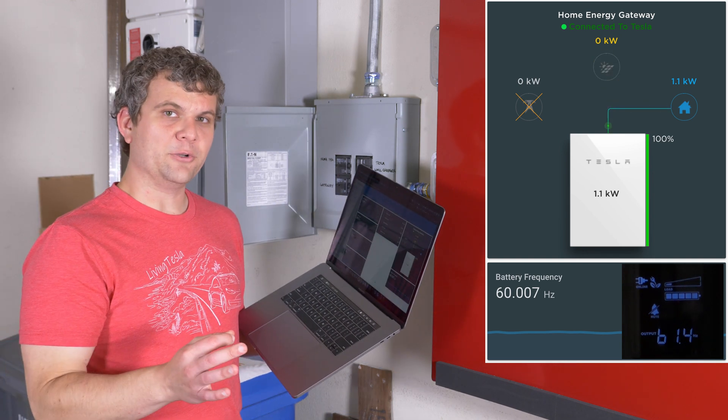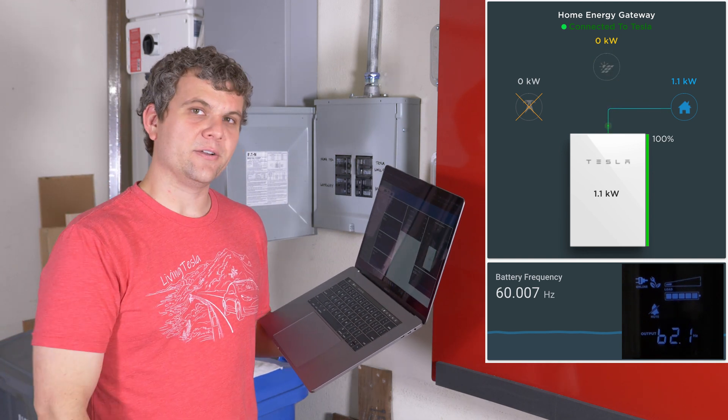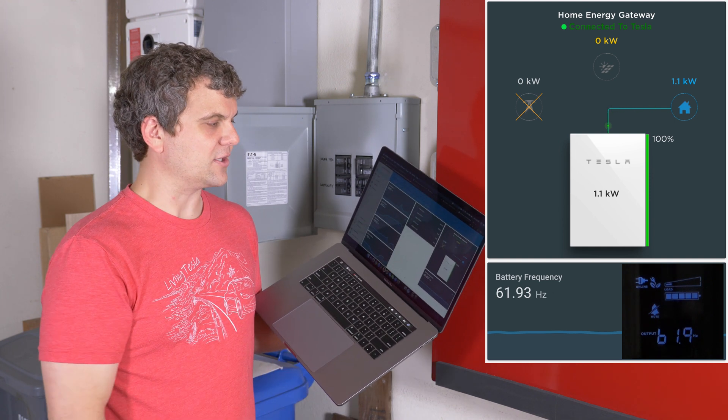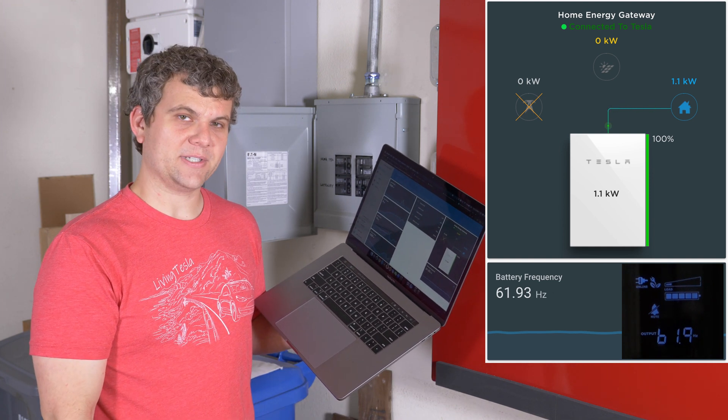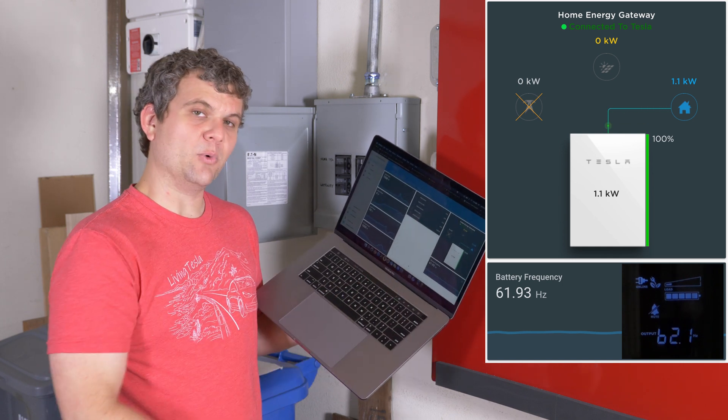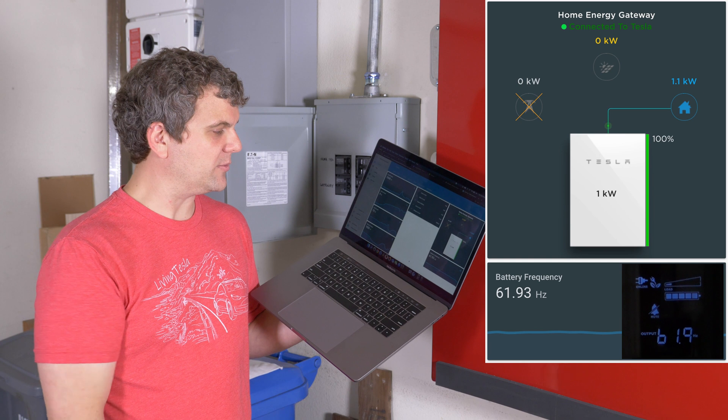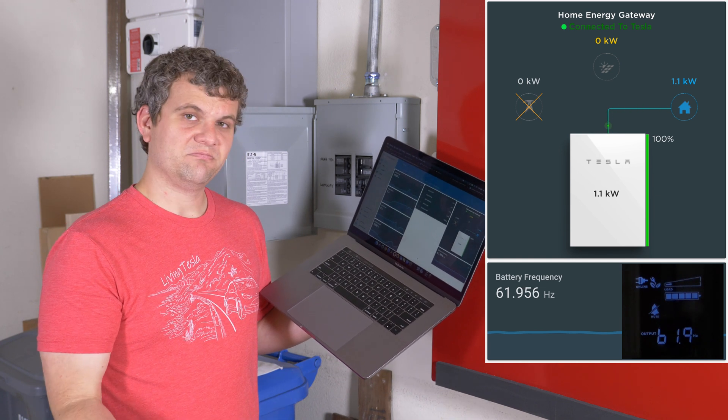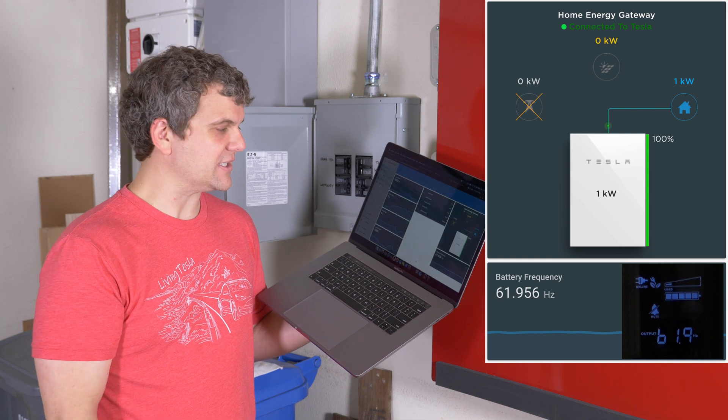So, we saw a little flash. I hear the inverter shutting down. Here on the display, solar is now at 0 kilowatts. Battery frequency is 61.93. It'll probably be 62 the next time it updates here. So that's it. 62 hertz instead of 60.